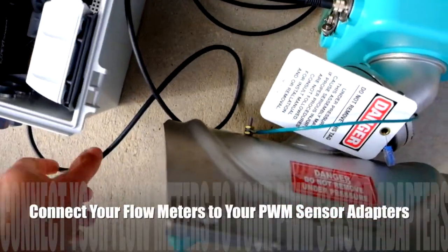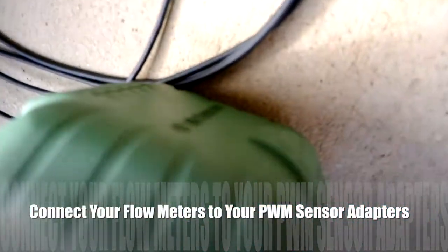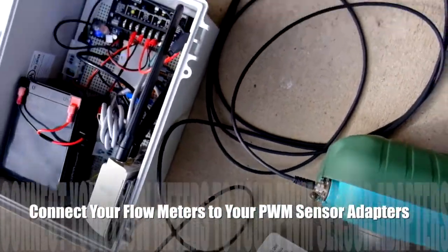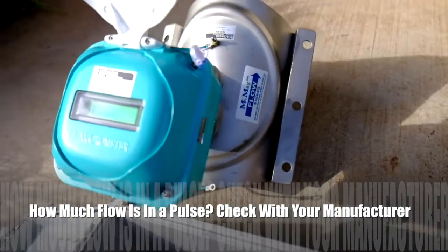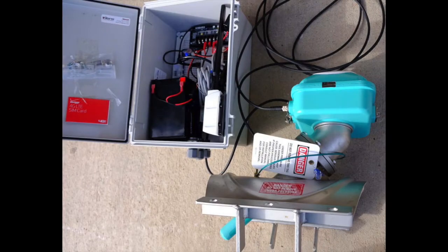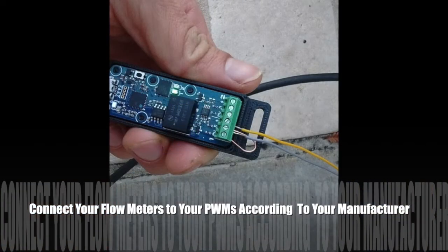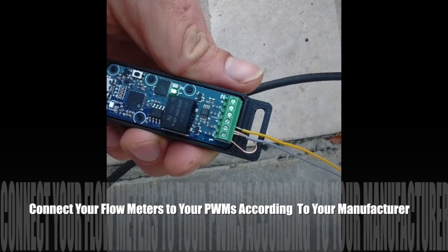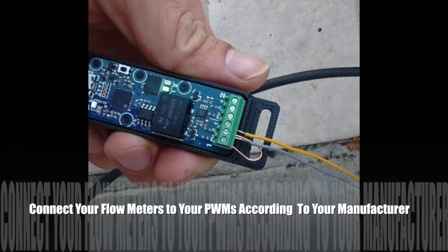We'll need to connect your flow meters to PWM sensor adapters so we can get water usage readings. You see there's a McCrometer pulse output cable that will attach to your PWM sensor adapters. Note this flow meter is set to output a pulse or tick for every 10 gallons that flow by. Make sure you double check with your sensor manufacturer to know what they've configured your pulses for. With the MCMAG 3000 there are yellow and gray cable leads. You'll connect your yellow lead to the ground connector on your PWM, and you'll connect the gray wire to the middle connector channel input slot, the one that has the PWM sensor input icon.